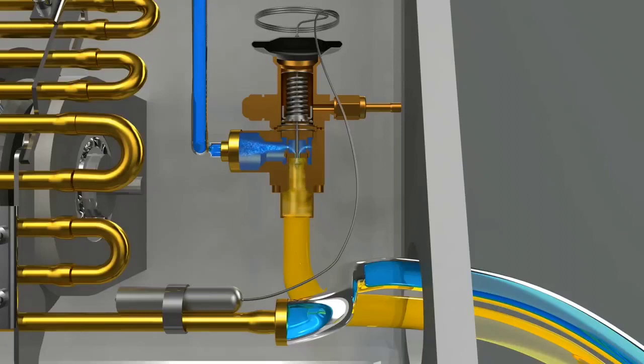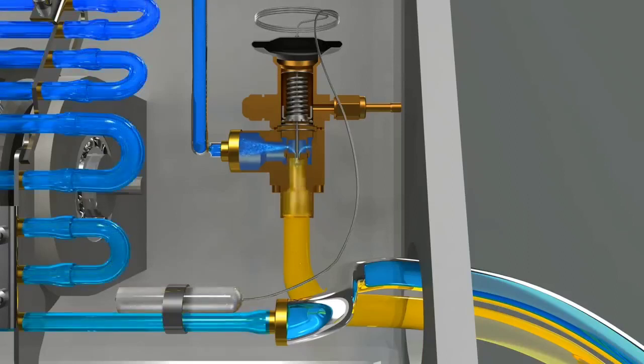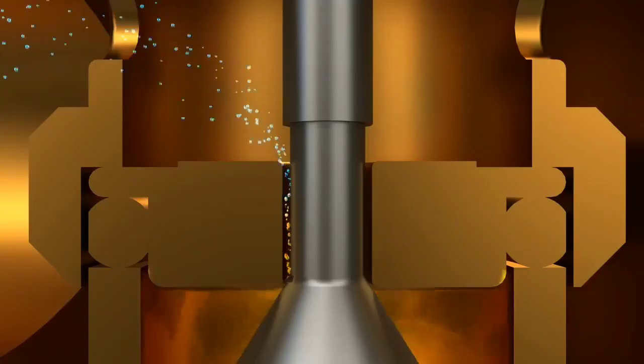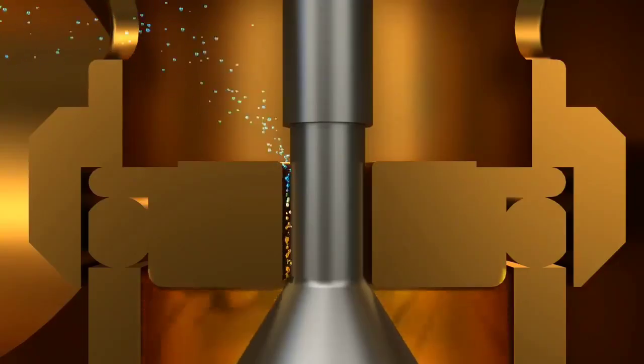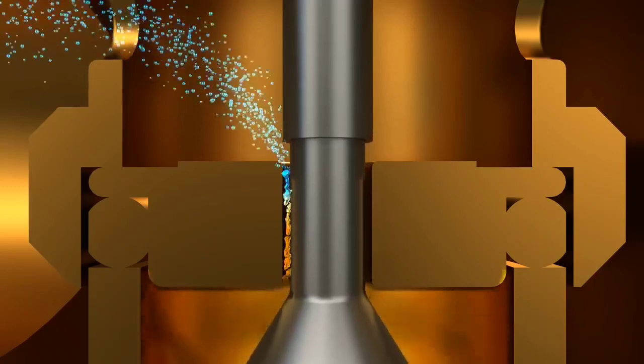Expansion valve is connected to sensing bulb that detects heat. Sensible heat storage is installed on the exit of an evaporator and detects temperature. Inside the storage is fluid sensitive to temperature changes, and as the temperature at the exit of an evaporator rises, the gas pressure rises, which in turn presses on a spring to send more refrigerant to evaporator.